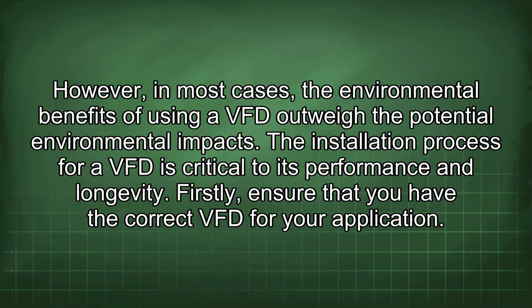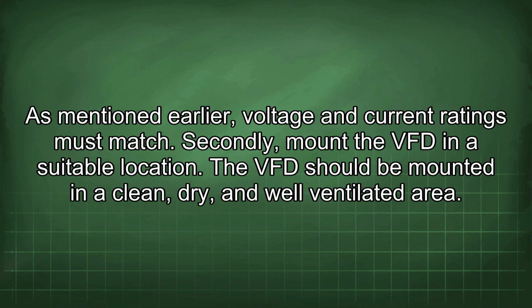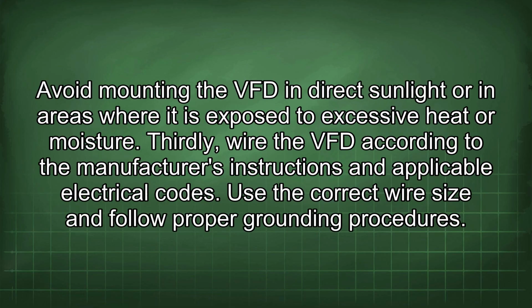The installation process for a VFD is critical to its performance and longevity. Firstly, ensure that you have the correct VFD for your application. As mentioned earlier, voltage and current ratings must match. Secondly, mount the VFD in a suitable location. The VFD should be mounted in a clean, dry, and well-ventilated area. Avoid mounting the VFD in direct sunlight or in areas where it is exposed to excessive heat or moisture.